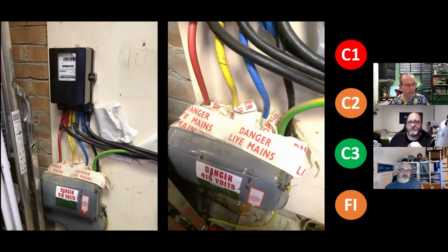It's obviously TNCS. Could it possibly be another end of line? Is it another end of line or three phase? That's my guess would be, if there's a separate cable going with it. There's only two logical choices with it. It's either an end of line earth rod, or they've done a repair on a PILC cable that's gone all the way through from the joint into the installation.